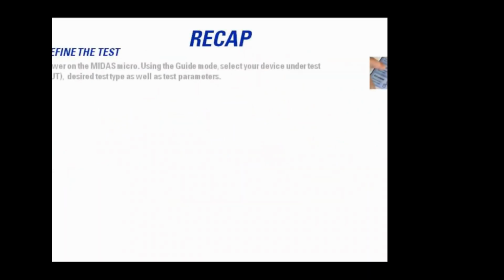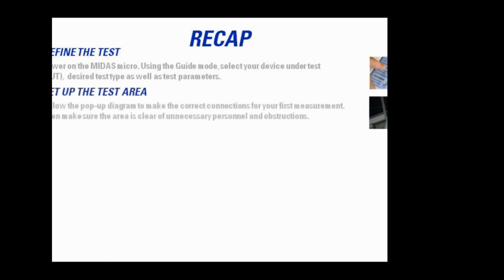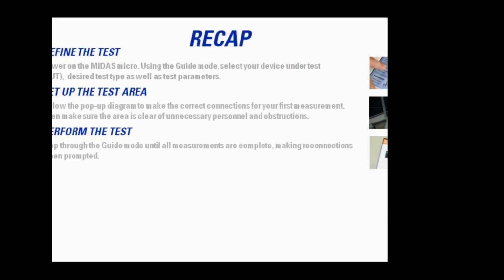To recap, define the test. Power on the MIDAS Micro. Using the guide mode, select your device under test, the desired test to perform, and test parameters. Set up the test area. Follow the pop-up diagram to make the correct connections for your first measurement. Prior to starting the test, make sure the area is clear of all unnecessary personnel and obstructions. Perform the test. Step through the guide mode until all measurements are complete, making reconnections when prompted.